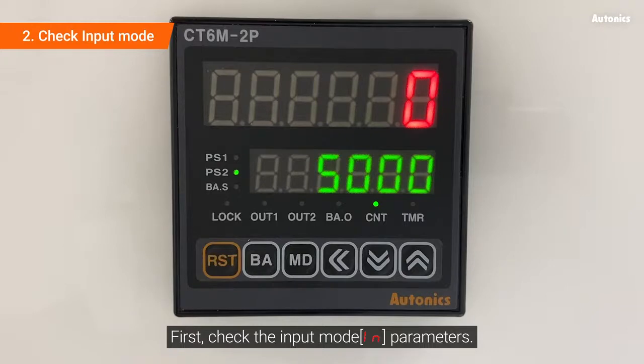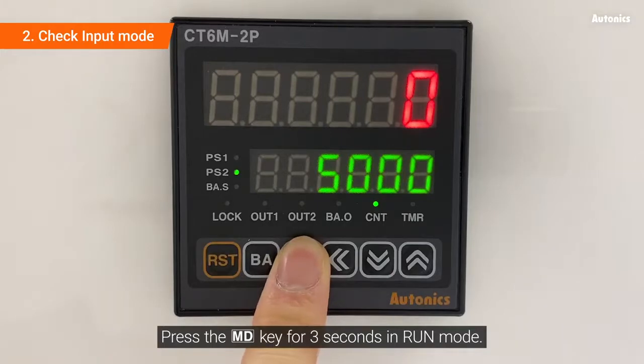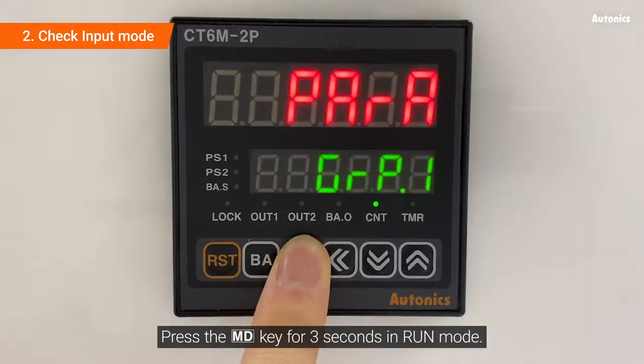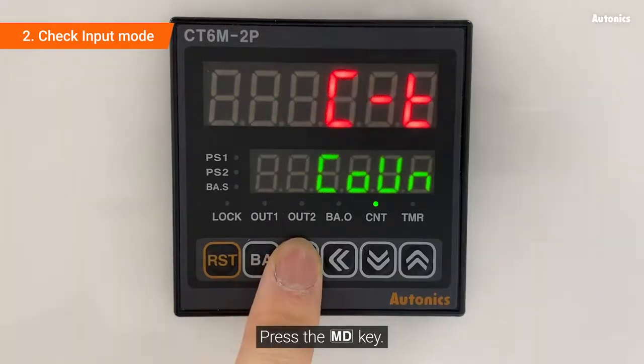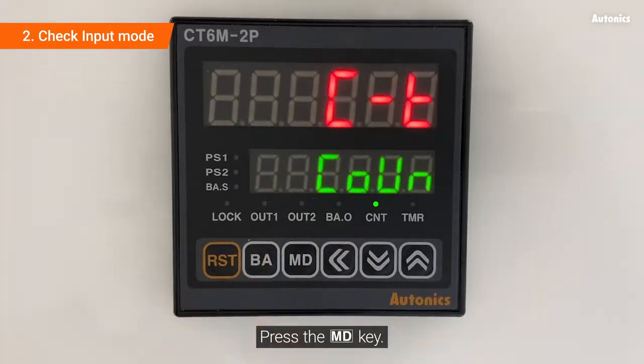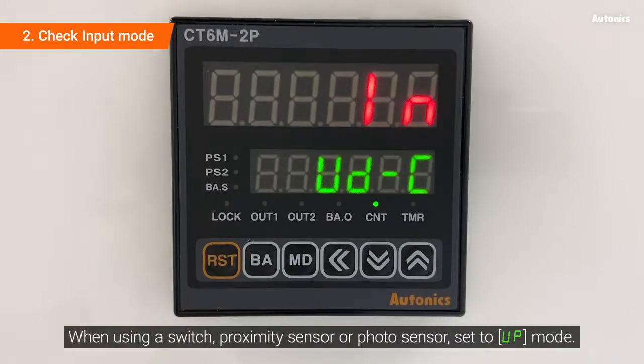First, check the input mode, IN parameter. Press the MD key for 3 seconds in run mode. Press the MD key. UD-C is an encoder-only mode. When using a switch, proximity sensor, or photo sensor, set to UP mode.